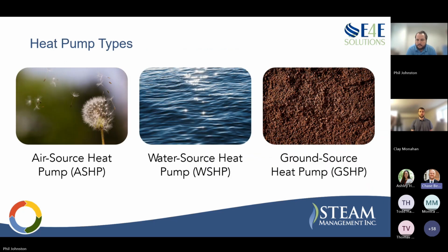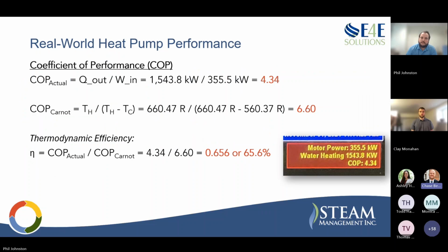I'd like to reiterate too that thermodynamic efficiency is not to be compared to a thermal efficiency. We're still well above 100% efficient. It's just a comparison of the actual efficiency compared to the ideal. Yeah, that's probably something to reiterate and plug into. So when we talk efficiencies, we can mix numbers up pretty quickly. This isn't accounting for basically the free energy you get from the heat source that would shoot that efficiency up much higher than a steam or a water heater, like Clay mentioned before. So you wouldn't really want to compare this efficiency to those. This is more comparing the COP you're achieving in actual terms versus the theoretical limit.